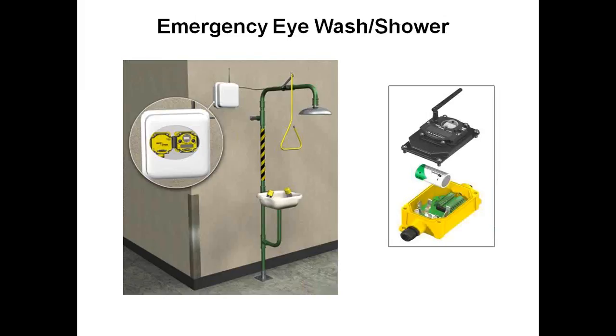The emergency eye wash is one that's becoming very common for us, where somebody has an eye wash station or shower. If this gets activated, they basically want to give a heads up to security. So we can put a node in here with a battery and run a discrete input. A lot of guys are actually putting flow sensors in line. What I'm showing over here to the right is, early on we had the separate battery module with a node. With another family we've got now, you can get the node where the battery is actually part of it, so now you've only got one piece. And we still have both versions. It just depends on if you want a plug-unplug battery or pop the top off and keep it in one piece. Again, if you have applications on this, let us know.